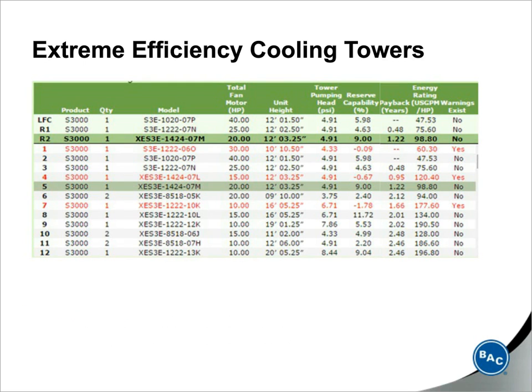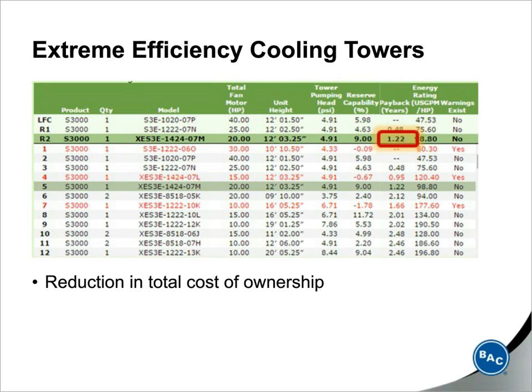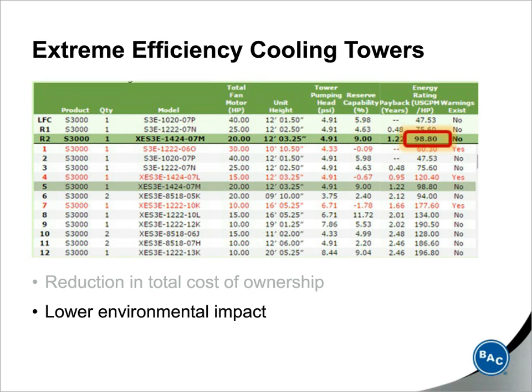So this is a screen capture of BAC selection software, and just to give you an idea of how to select these towers. By evaluating energy ratings and different payback periods, owners can really save quite a bit of energy. In this particular selection, the third model listed offers half the horsepower as the lowest first cost model in just over a 1-year payback. And now compare this extreme efficiency cooling tower energy rating.